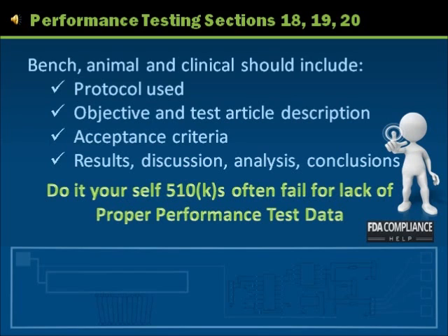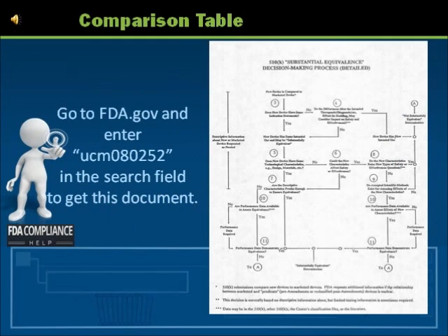Now, let's go to the detailed substantial equivalence flowchart. This detailed substantial equivalence decision-making chart will serve as an interim review. Starting with question 3, does new device have same indication statement? In question 3, if the answer is no, then question 4, do the differences alter the intended safety and effectiveness?